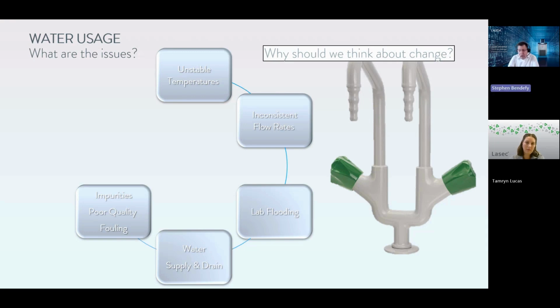Many companies globally may use well water or bore water to provide their cooling water. We would strongly recommend against this, as the impurities that would be in that water would be very damaging to any machine that they may have. We spoke earlier about the use of spectrophotometers of different types, and we would want to avoid long-term fouling or contamination of those water cooling systems inside that rather costly equipment, valuable equipment that provides an important service. If the maintenance of that equipment is not kept up and fouling occurs, then we're damaging those machines.